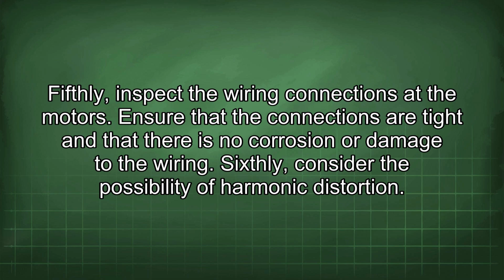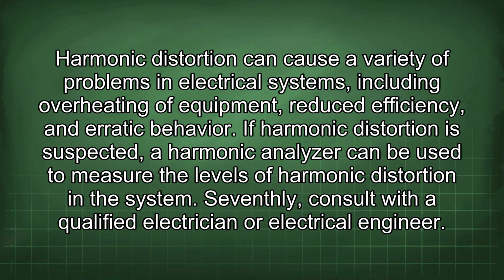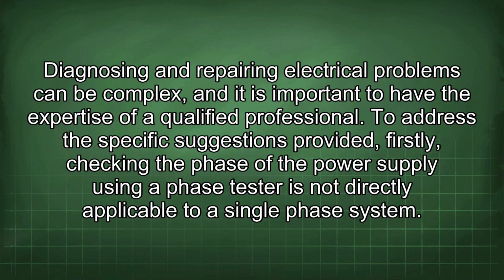Sixthly, consider the possibility of harmonic distortion. Harmonic distortion can cause a variety of problems in electrical systems, including overheating of equipment, reduced efficiency, and erratic behavior. If harmonic distortion is suspected, a harmonic analyzer can be used to measure the levels of harmonic distortion in the system. Seventhly, consult with a qualified electrician or electrical engineer. Diagnosing and repairing electrical problems can be complex, and it is important to have the expertise of a qualified professional.